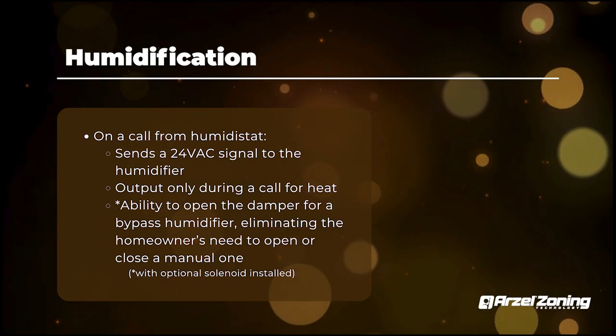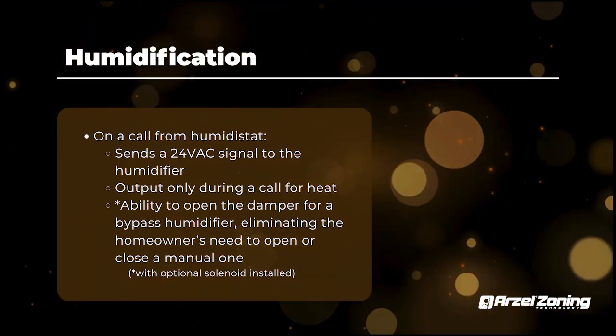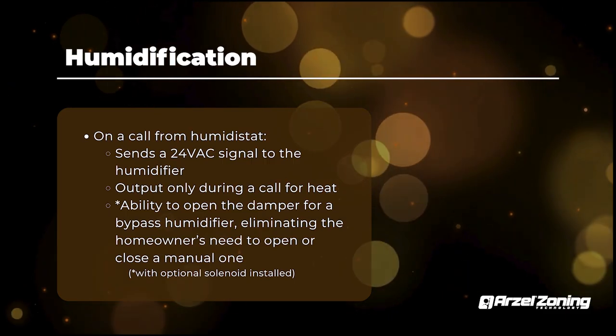They are 24 volts. So on the output of the panel, it'll have an H terminal that does supply 24 volts out with a call for humidity.